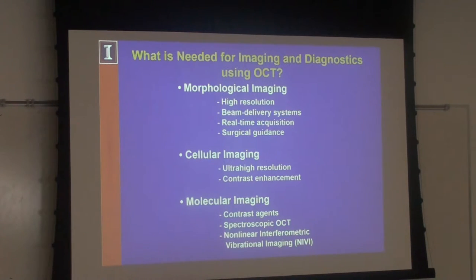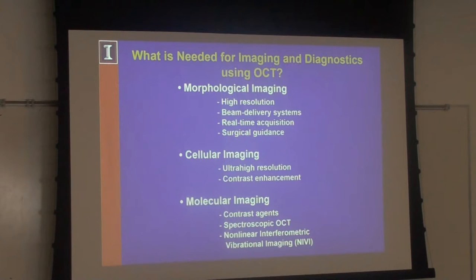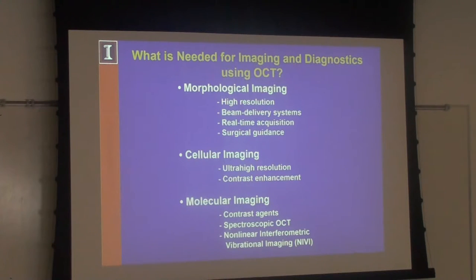For a retinal scan, you need mirrors to scan across the back — that's correct. People have also looked at line-field scanning: instead of scanning a point across, you create a line and scan that, using a 2D detector instead of a spectrometer. Some have done full-field OCT where you have a full field beam across the tissue and interfere it with full field in the reference arm, though there are disadvantages including crosstalk from multiple scattering.